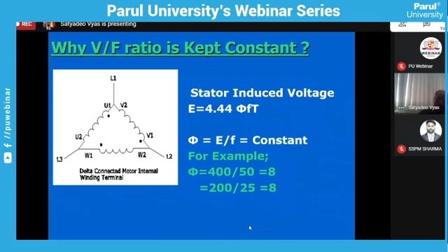So when we reduce the frequency, we reduce the voltage also. In this case, you can see I am reducing the frequency from 50 to 25. Then I will have to reduce the voltage from 400 volt to 200 volt, so that I can maintain the flux in the air gap constant at the rated flux of the motor.